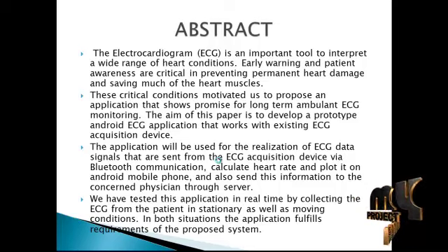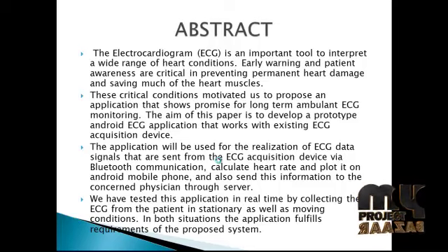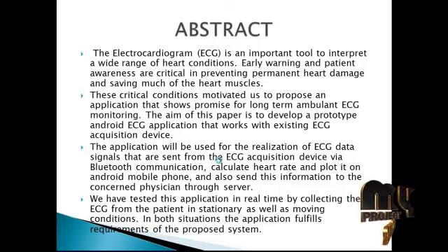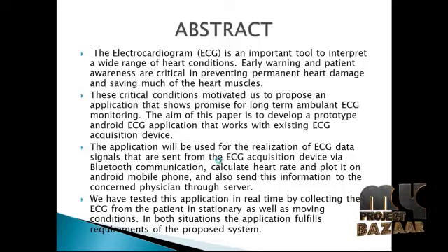We will be using 3 ECG sensor electrodes to measure the ECG signal. A biopotential electrode is a transducer that senses ion distribution on the surface of the tissue and converts the ion current to the electronic current. An electrolyte solution is placed on the side of the electrodes.